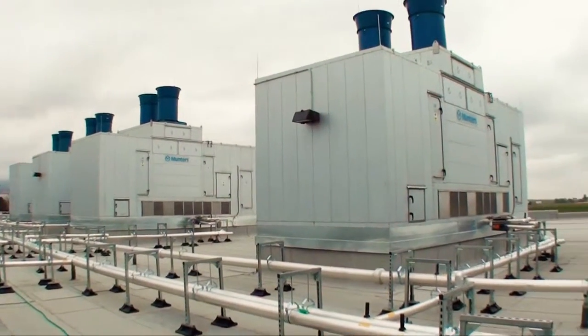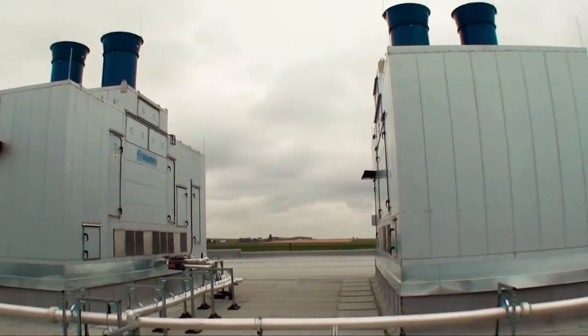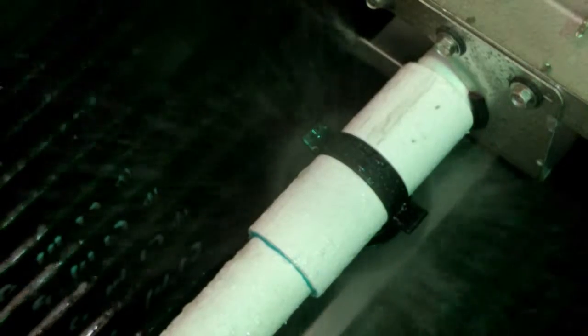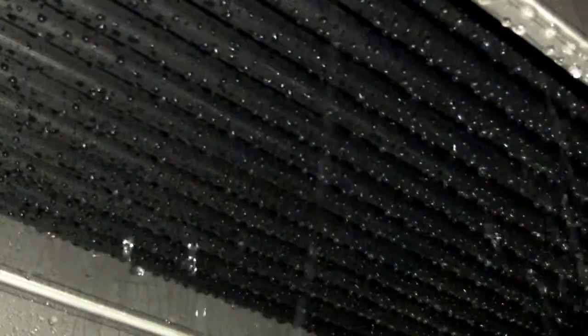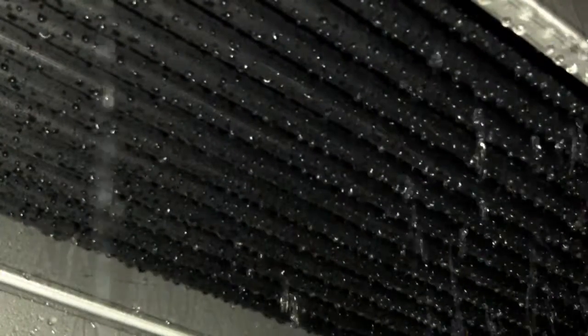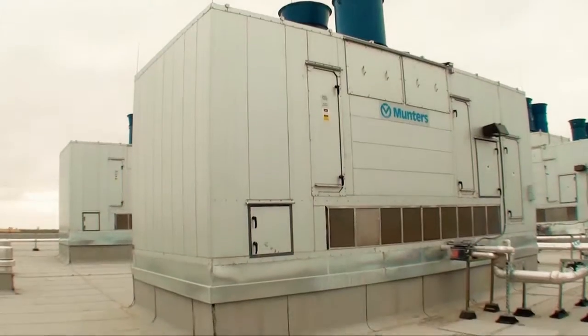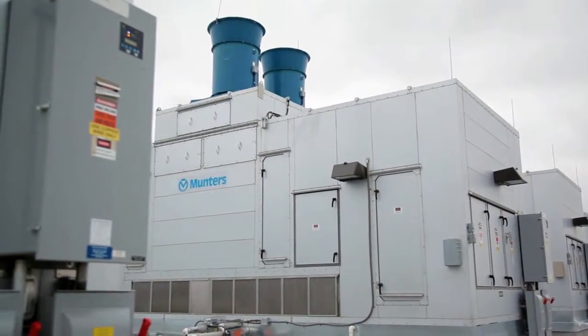This summer, actually in July, we commissioned the second half of our co-location data center here at Sabey Data Center in Intergate, Quincy, and we saw a PUE of 1.25, and we really commissioned that data center hard. We had fan units that were simulating servers to make sure that we were actually running these units at full airflow. And very impressed. We were not expecting to get 1.25 on a hot July afternoon on our PUE, and we saw that in commissioning, and I think realistic commissioning. The Munters Oasis indirect evaporative cooling unit has exceeded our expectations. We've been very, very satisfied with both the air handlers and with Munters as a company and supporting their air handlers.